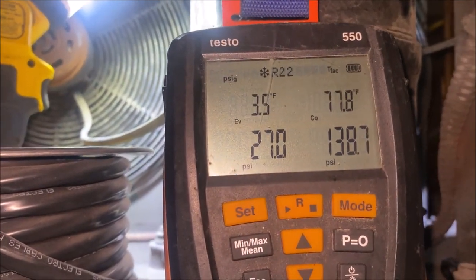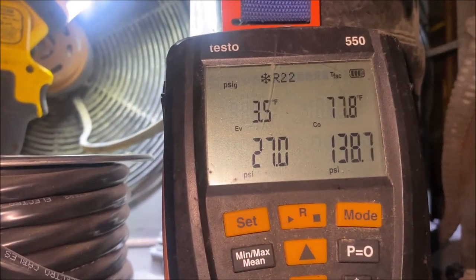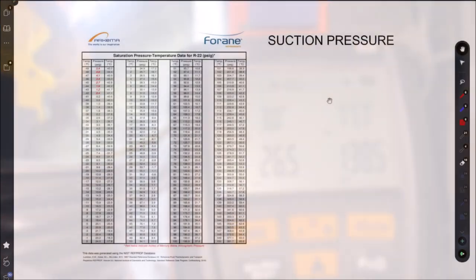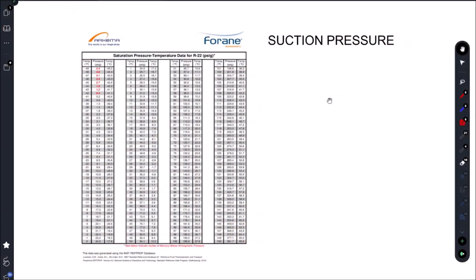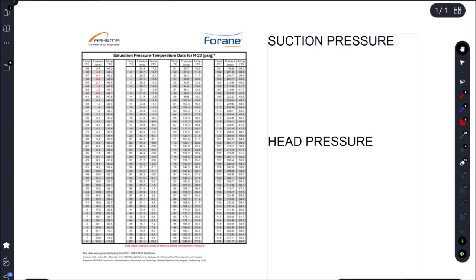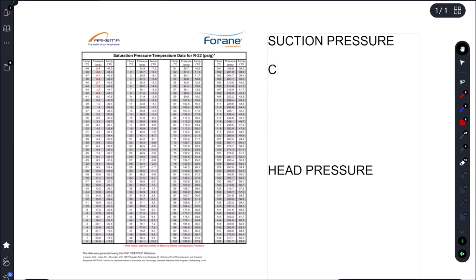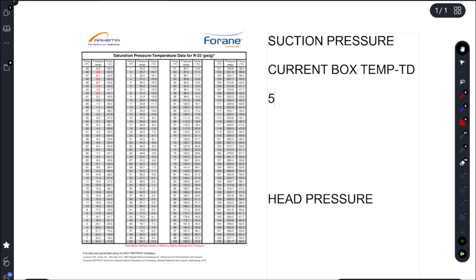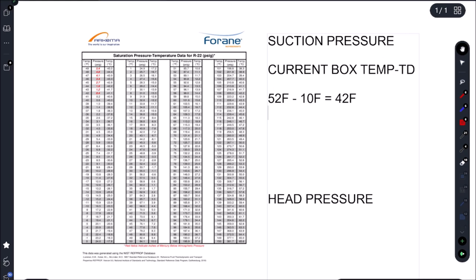Good thing we know what our saturation temperatures need to be so we don't need a sight glass, we can figure this out on our own. Alright, so let's pull up an R22 PT chart and let's figure out what our pressures and saturation temperatures need to be. In order to figure out our suction pressure we simply take our current box temperature and we're going to subtract our evap TD. So our current box temp was 52 Fahrenheit and our evap TD because it is a walk-in cooler is going to be approximately 10 Fahrenheit but it's going to be set by our superheat. So that gives us 42 Fahrenheit.